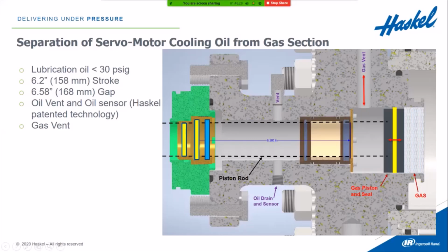The left-hand side here represents the servo drive itself. This green would be the lubrication oil that's in the servo drive. We have several seals in there. We have 2 oil seals, and then we have an oil seal with a wiper, right here is the blue line. This dotted line represents the piston rod itself. Then we have a couple of gas seals with a wiper seal in there also. And then this is our gas section.